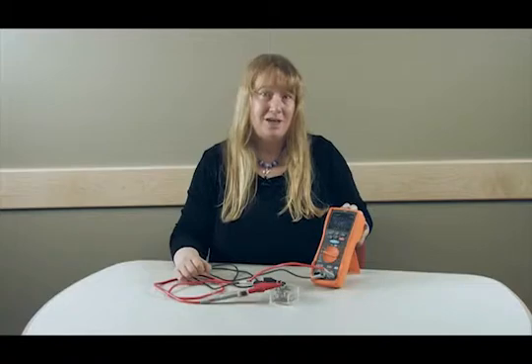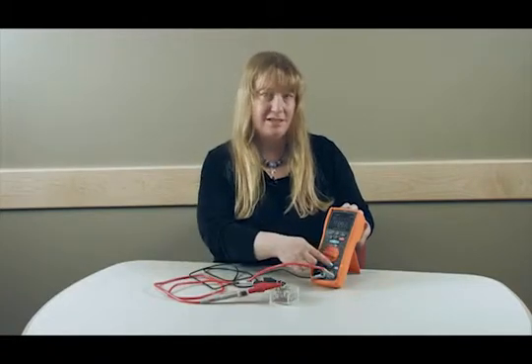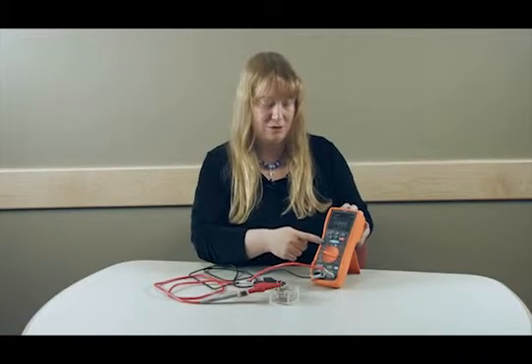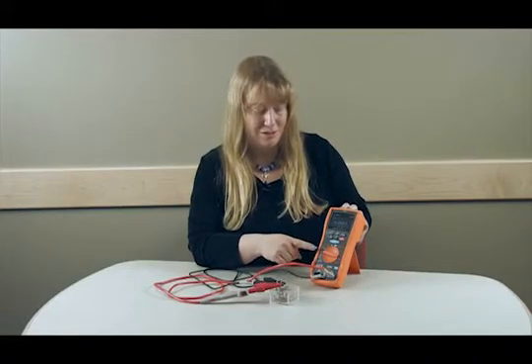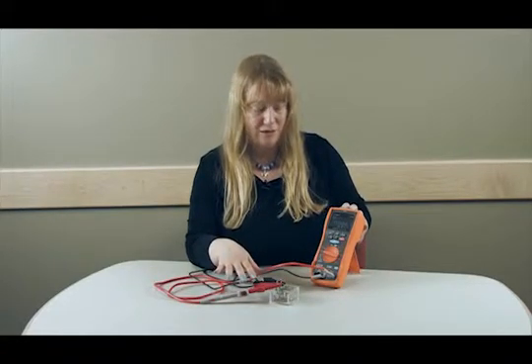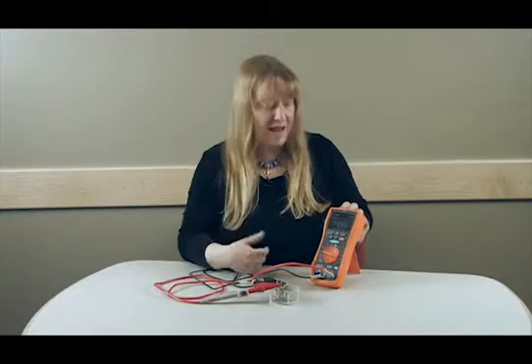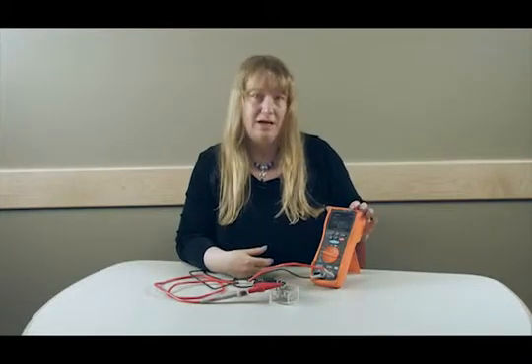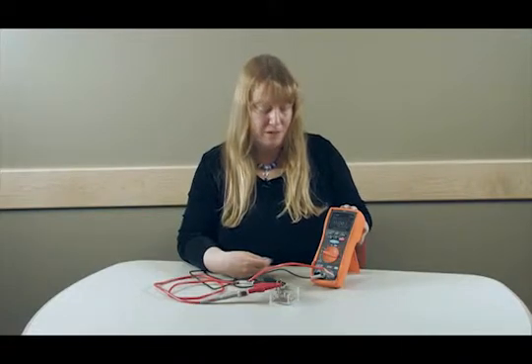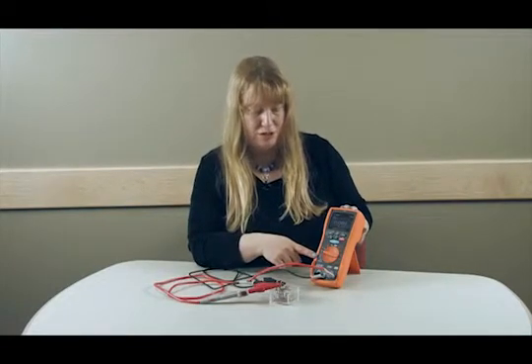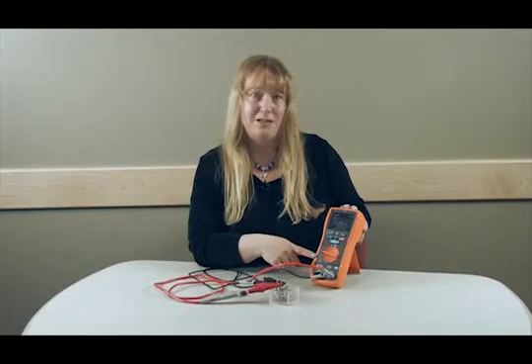It's also really helpful to have an instrument that not only has the insulation measurement side, but also a full-fledged DMM function. It allows you to test for your live voltages. It has an ambient temperature reading since insulation measurements are greatly affected by temperature. It also has the ability for you to use a direct temperature measurement to get a more accurate reading of your device under test.